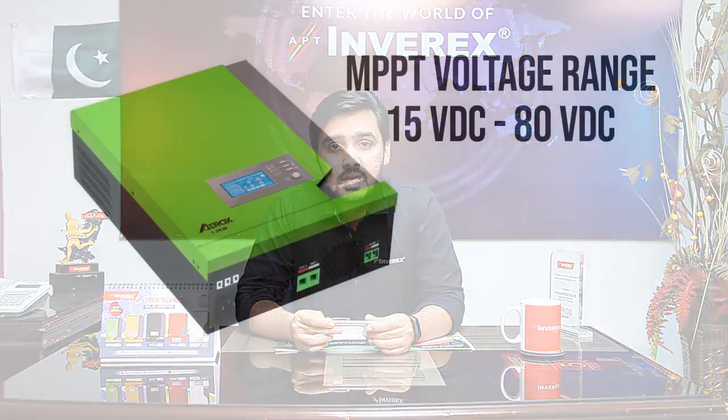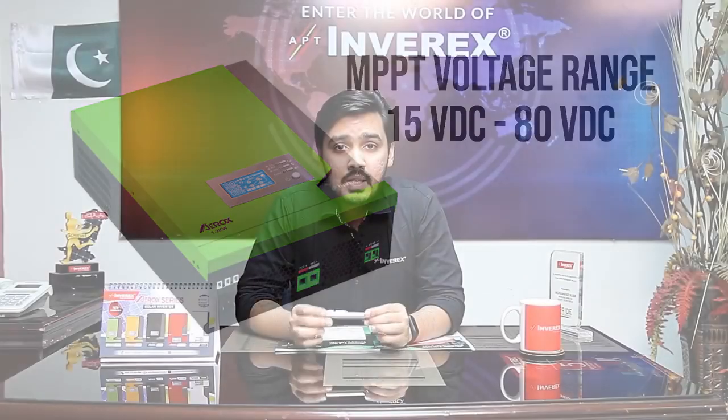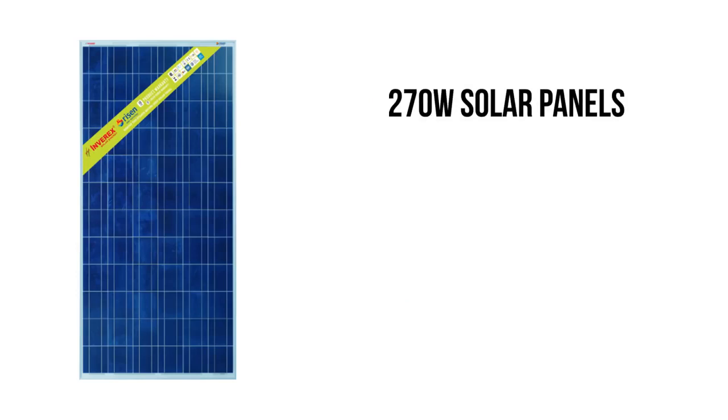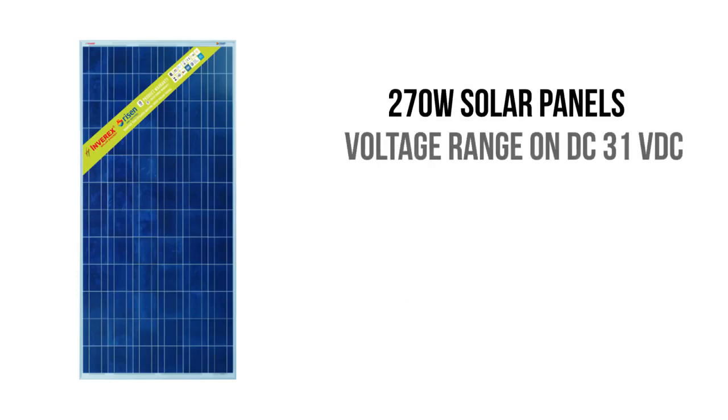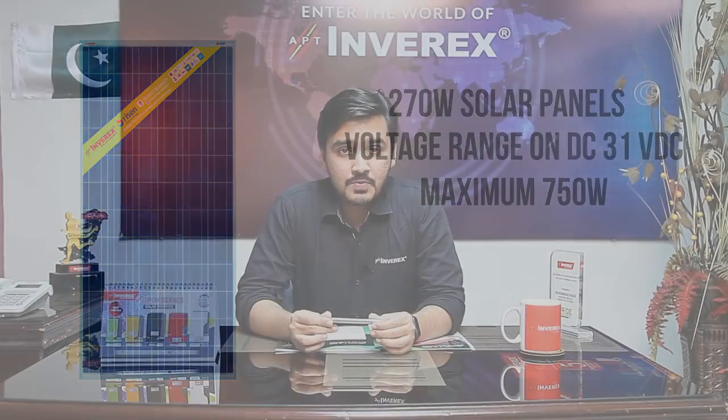Now we will learn how solar panel connections can be made with this inverter. As mentioned earlier, the MPPT voltage range of this inverter is 15 VDC to 80 VDC, which enables you to connect solar panels in series as well. Inverex's Ryzen 270 watt solar panels have a DC voltage of around 31 VDC under load, meaning you can connect two Ryzen 270 watt panels in series with this inverter and stay within the 80 VDC range. The maximum solar panel capacity for this inverter is 750 watts.